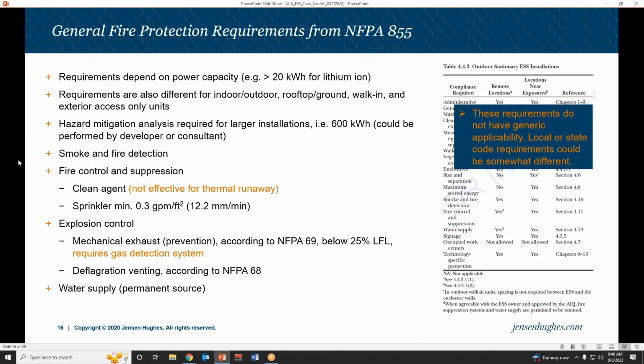NFPA 855 recommends a sprinkler density of 0.3. New York City requires a sprinkler density of 0.5, so it's a lot of water. Why am I telling you what New York FDNY does? I think they are a little bit ahead — they now put energy storage systems in all these new high rises. You can also obtain it when you Google it; FDNY has their own standard called Rule 608. It's pretty good, provides some background.